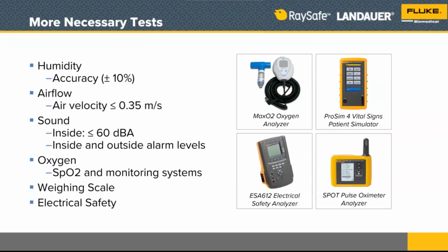All right, and here's some more measurements that we need to make and the accuracies that are needed. These come right from the standard. The humidity, the airflow needs to be less than or equal to 0.35 meters per second. Sound pressure level, oxygen concentration, the scale, and then our electrical safety checks. So it's not just an infant incubator analyzer that you need. You also need some other test instruments to make sure you're covering all of the parameters and getting those measurements done appropriately.